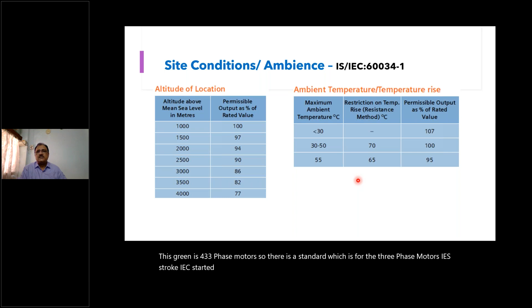So there is a standard for the three-phase motors, IS/IEC. It's called a dual standard, 60034-1. Now IS 325 used to be the standard till almost 2017-18. This got changed and we adopted the IEC standard as a dual standard, IS/IEC 60034-1. There are a few engineers, few technical consultants who continue to use IS 325. IS 325 is retired and it's no longer available. But the fact is most of the IS 325 standards are retained under IS/IEC 60034-1.